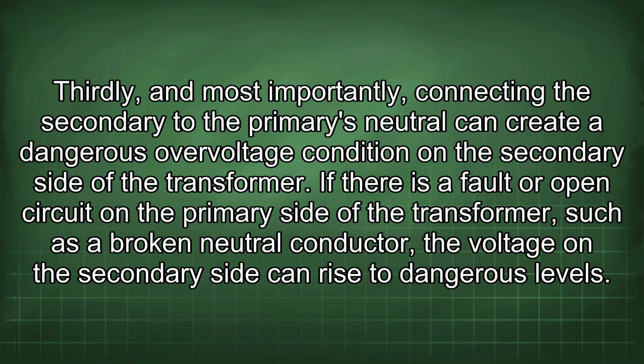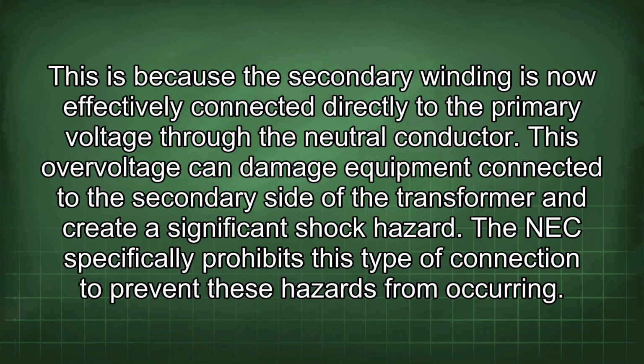Thirdly, and most importantly, connecting the secondary to the primary's neutral can create a dangerous overvoltage condition on the secondary side of the transformer. If there is a fault or open circuit on the primary side of the transformer, such as a broken neutral conductor, the voltage on the secondary side can rise to dangerous levels. This is because the secondary winding is now effectively connected directly to the primary voltage through the neutral conductor. This overvoltage can damage equipment connected to the secondary side of the transformer and create a significant shock hazard. The NEC specifically prohibits this type of connection to prevent these hazards from occurring.